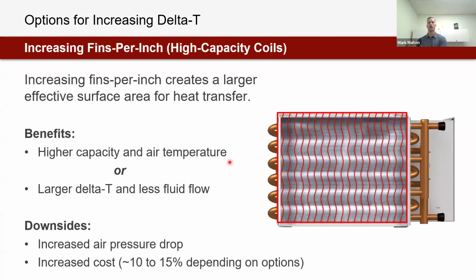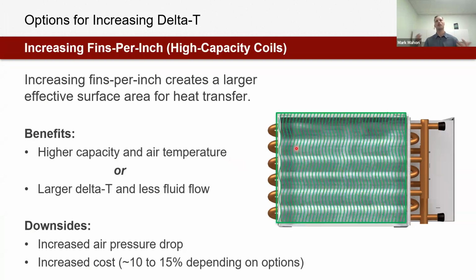And so historically, there was two options. We could increase fins per inch, and increasing fins per inch means we're going to have, looking at a width cross section on screen here, we're just going to increase the number of aluminum fins in each inch segment as we move from left to right across the coil.